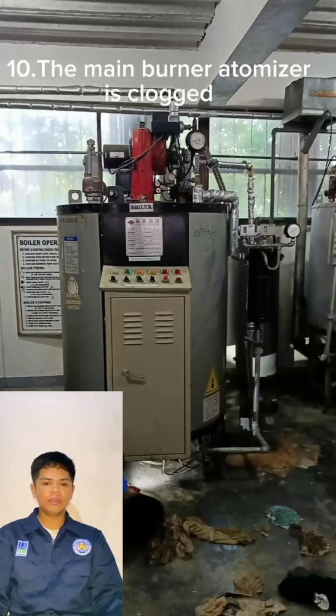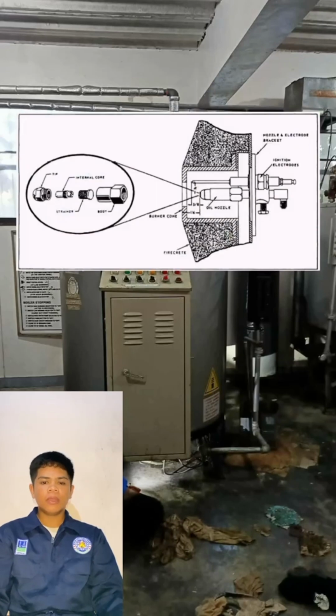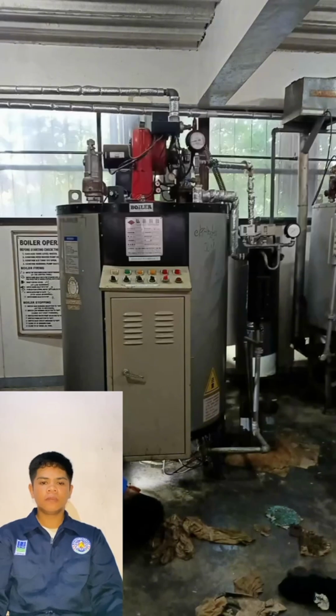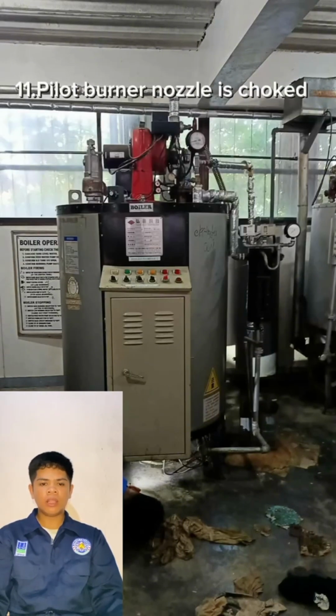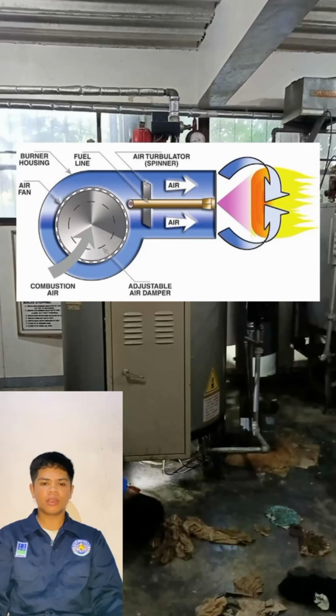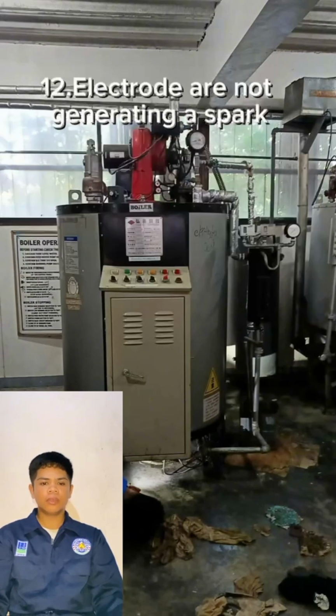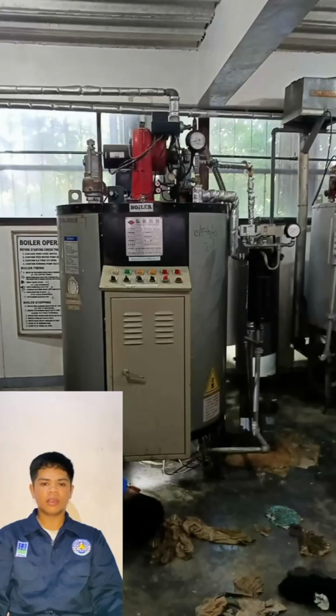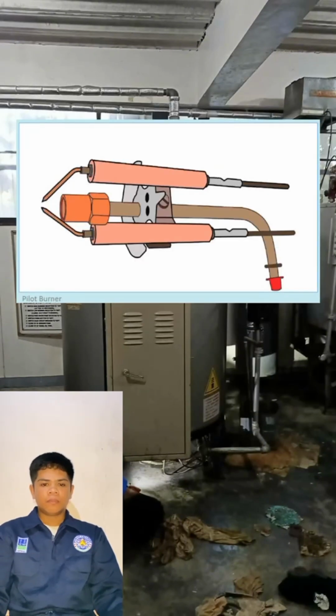The tenth is that the main burner atomizer is clogged. The main burner consists of an atomizer for efficient burning of fuel. If the atomizer is clogged by sludge and fuel deposit, then the burner may not produce flame and trip the boiler. The eleventh is that the pilot burner nozzle is choked. A pilot burner nozzle is very small and can be blocked by carbon deposit and sludge, resulting in flame failure. Lastly, the electrodes are not generating a spark. The initial spark for generating a flame is produced by the electrode.